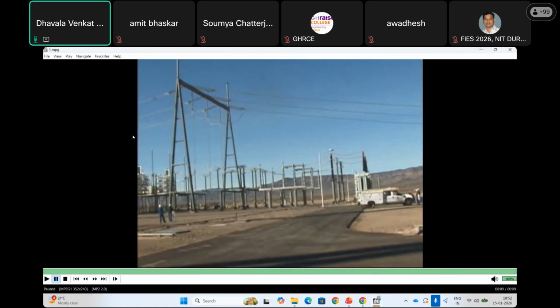So now, what is this? This is a 765 kV switchyard where isolators are auto-operated. What is the harm if one gets stuck or has some technical fault - what can happen? For this we have to take preventive maintenance, predictive maintenance, even breakdown maintenance. Apart from that, in totality, it is CBM technology where we can manage everything in a good manner.